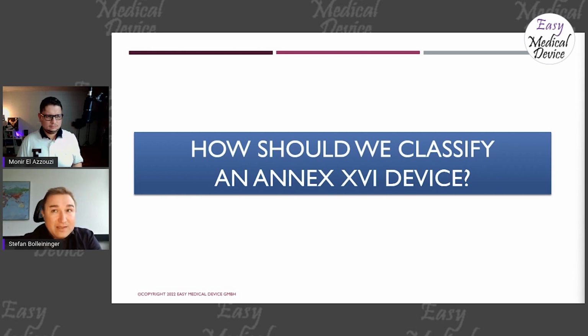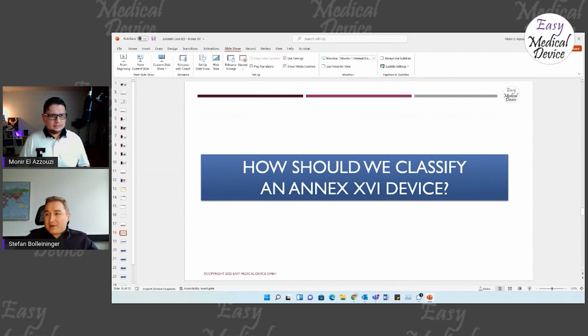And now, giving it into the implementing regulation, you won't find any hint about classification anymore. So it's completely up to you to decide how you want to do it, and then talk with your regulatory agency. So actually now, when I look into it, for nearly maybe all active devices which fall under Annex 16, from my perspective, I would first strike into a class 1, go to my regulatory body, my agency, my local competent authority, and ask them, is that my opinion, is that right or not? And then go to the notified body if needed. But at first, I would go directly to the competent authority, because they can tell. All others, it's pretty open what you think about.